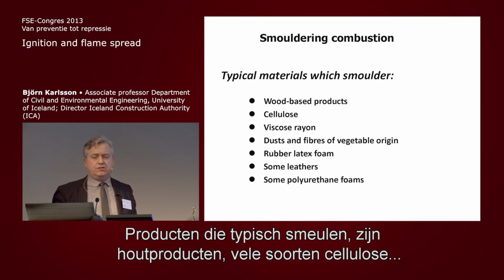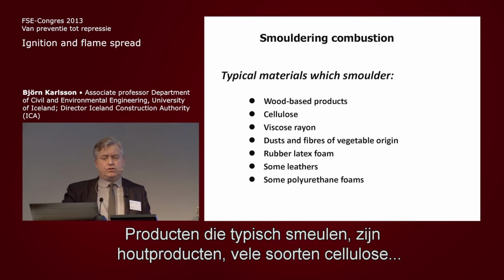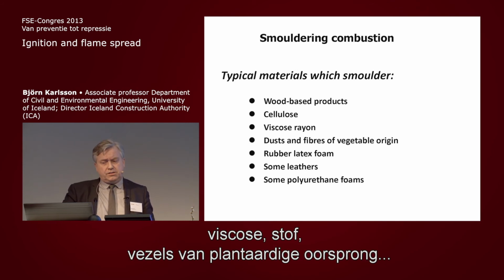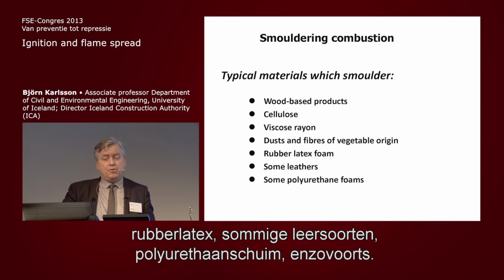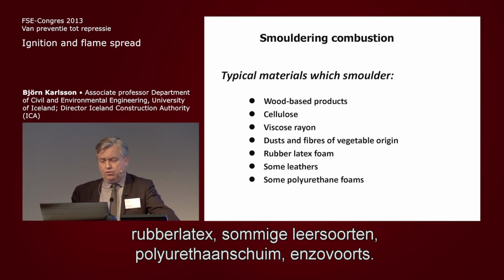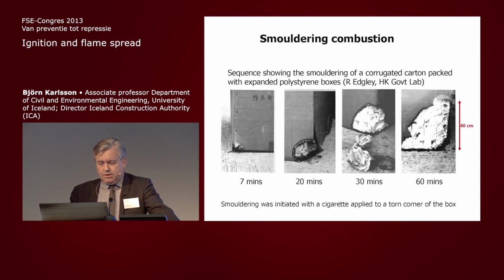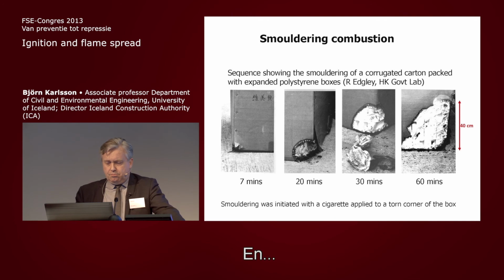Typical materials that smolder: wood-based products, all kinds of cellulose, rayon, dusts and fibers of vegetable origin, rubber latex, some leathers, polyurethane foams, and so on and so on.